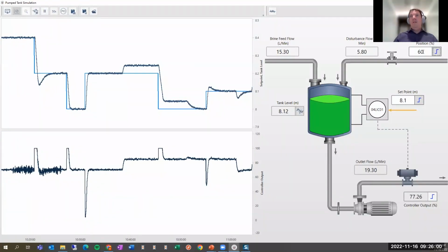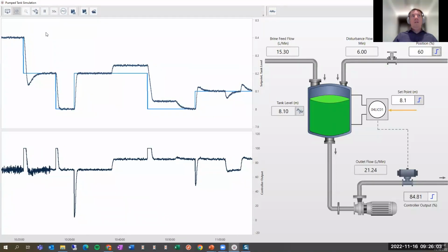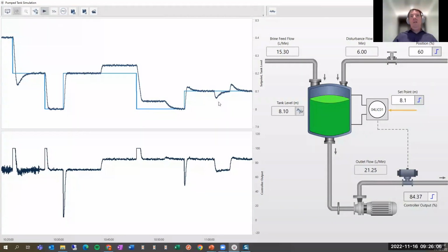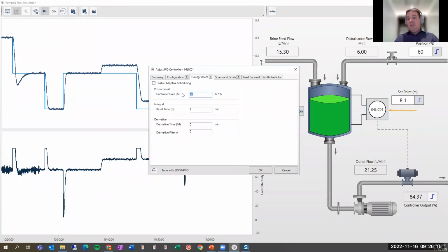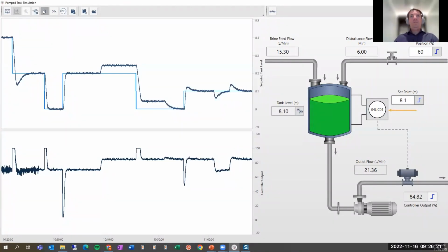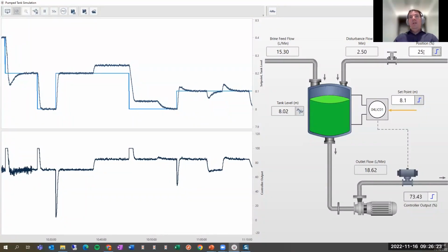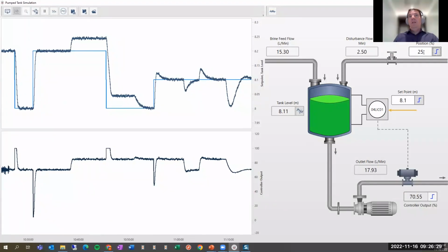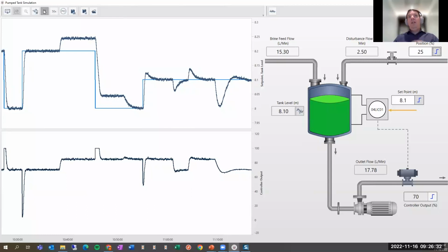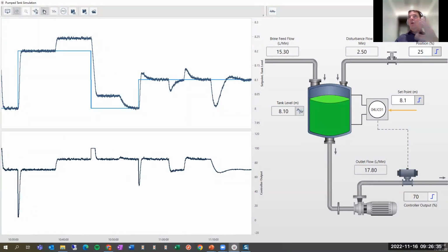Okay, so go back to 16. That's usually what you will see. Disturbance, go back to normal. Disturbance, go back to normal. What we have here again is the aggressive gain. So we'll see the disturbance rejection if I use a lower gain. So if I go back, not only in a set point change, a low gain on your controller was not really good. Same thing with the load rejection. It will not help you at all.